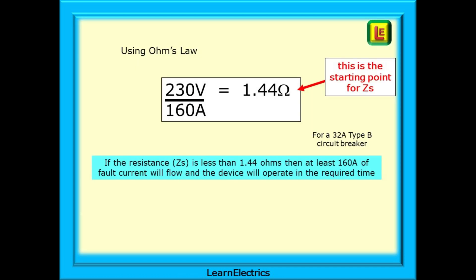Using Ohm's law we can calculate what value of circuit resistance will allow 160 amps to flow. We always use 230 volts, the nominal voltage, for our calculations. 230 volts divided by 160 amps gives us 1.44 ohms. We now know that if a resistance or ZS is less than 1.44 ohms then at least 160 amps of fault current will flow and the 32 amp type B breaker will operate in the required time.